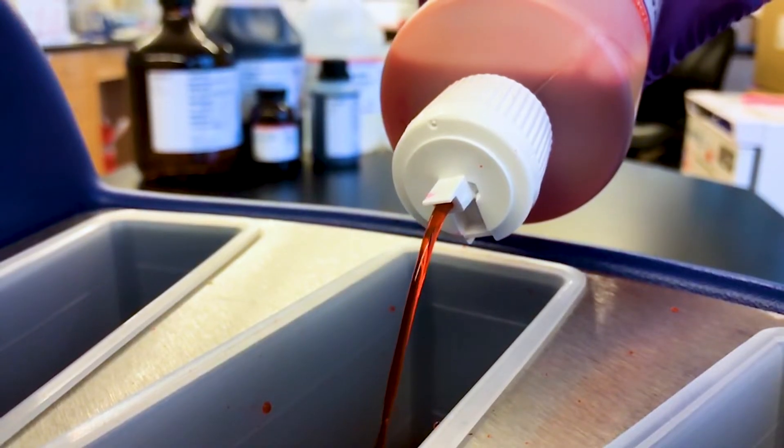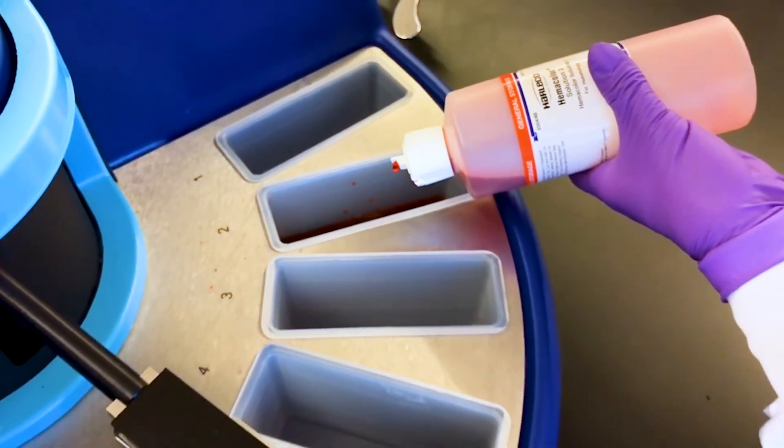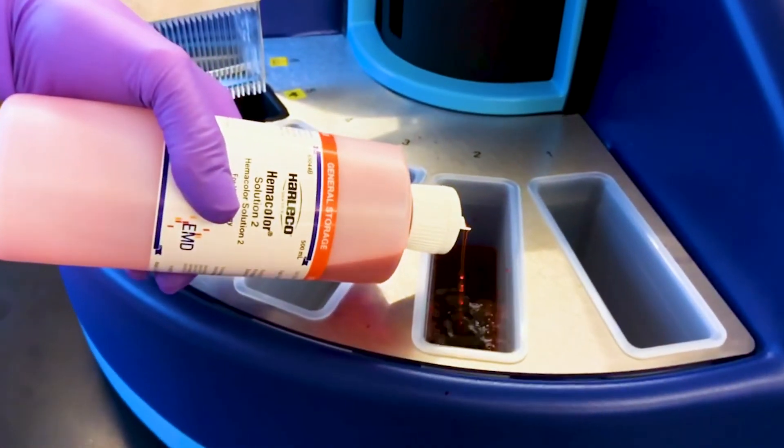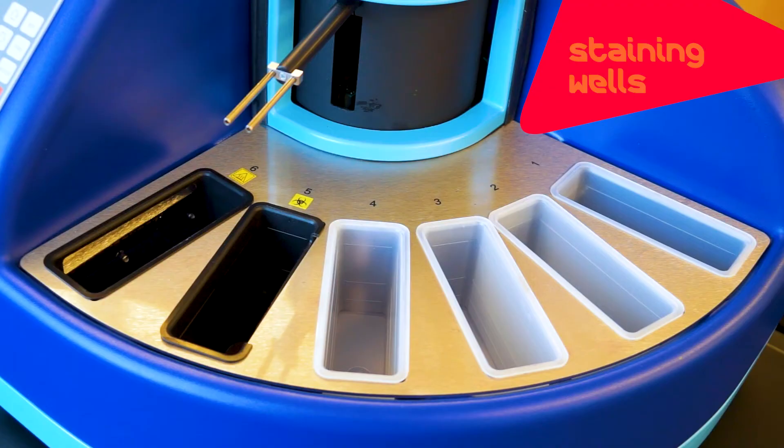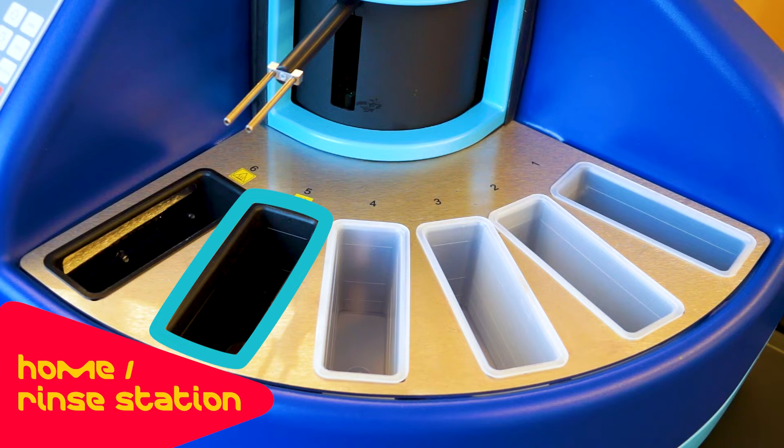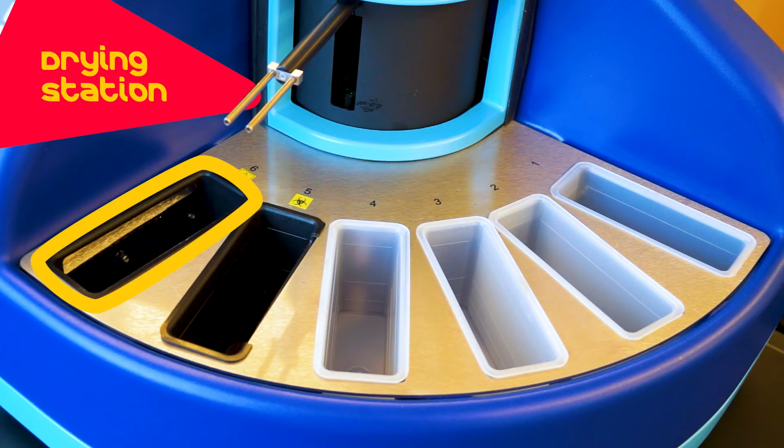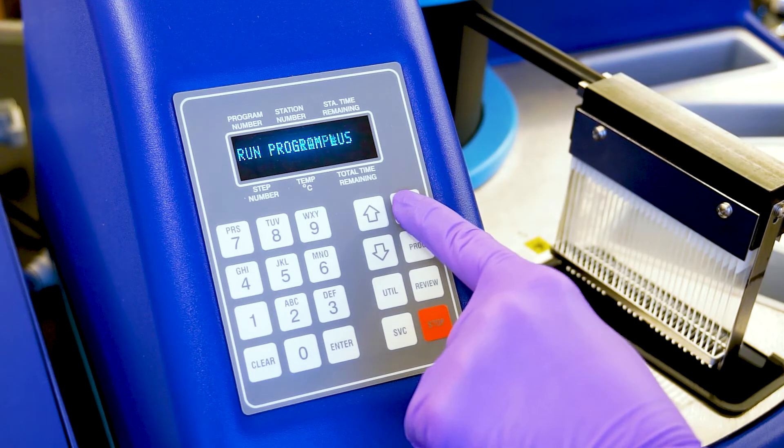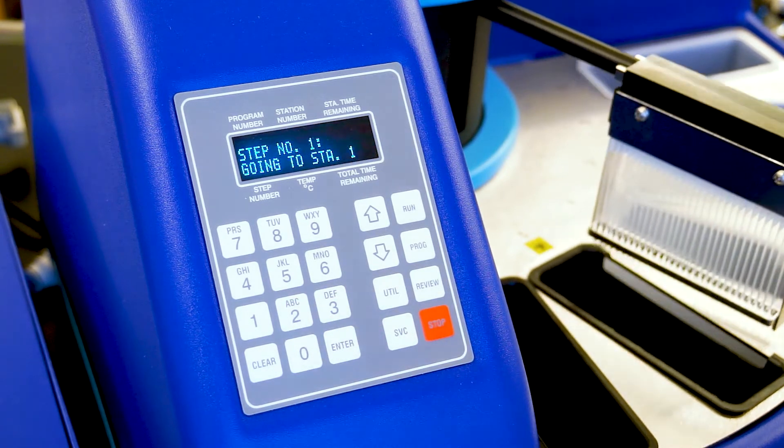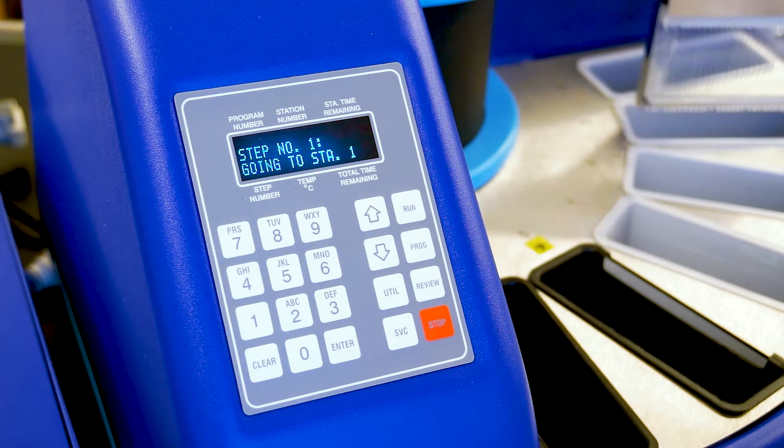All reagents are placed in removable plastic wells which mount in the unit. Fill up four of the wells to match the staining protocol and change when necessary. In addition to the four staining wells, the Midas 3 Plus has both a rinse station with circulating water and a drying station. Once the slides are mounted and the wells loaded, all that is necessary is to retrieve the stored staining protocol via the keypad and set it in motion.